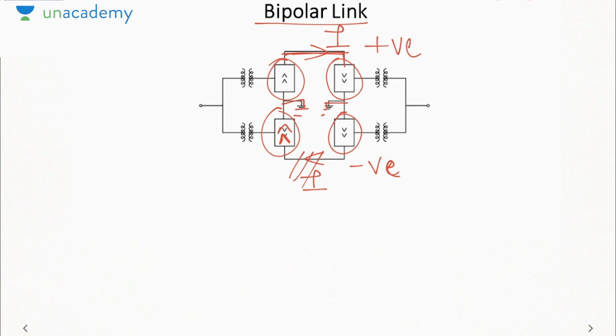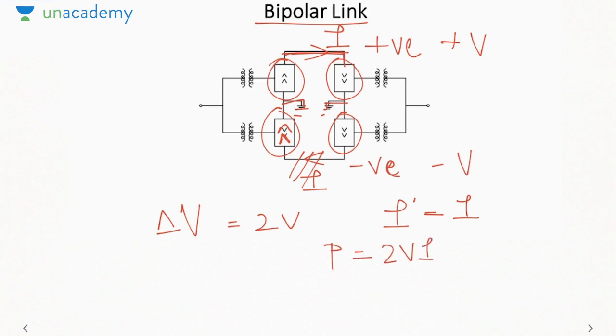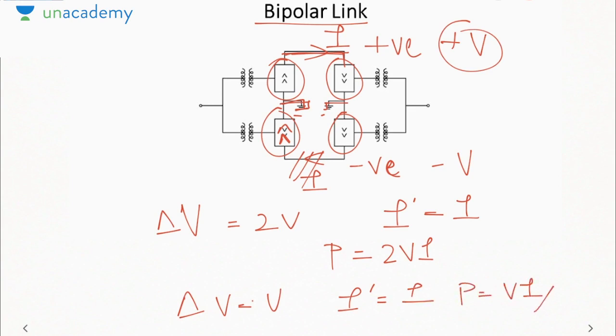When one conductor in a bipolar link breaks down, it will operate as a monopolar link with a reduced capacity. Why reduced capacity? Because the voltage will be halved. Suppose this is plus V, this is minus V. The potential difference will be 2V. Current is I, so power will be 2VI. But if one conductor breaks down, the voltage will be plus V here and 0 there, so delta V will be V. Current would still be I. Power will be VI. So power carrying capability will become half, but it can still supply some power to the load. But in case of a monopolar link, if one conductor breaks down, supply is interrupted. So that is the advantage of the bipolar link.